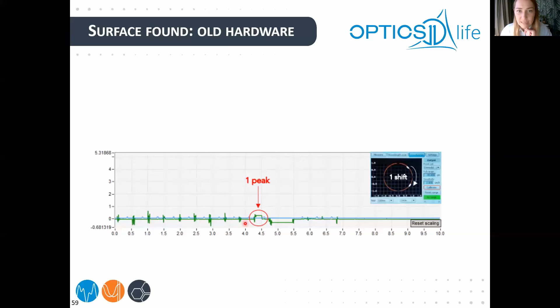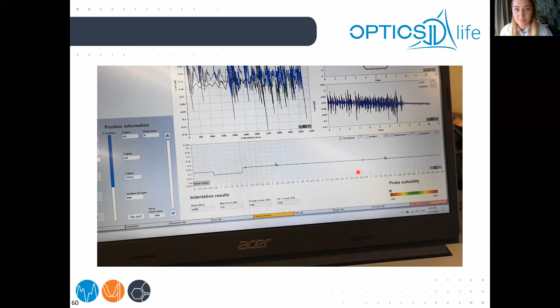Now, if you're not sure, you missed it, or you want to double check, you can just check manually. So what I did here, I moved down, and I see that there is a change in the baseline, and then I'm moving up, up, up, up, up, and here I'm out of contact. So I continue to move up and the baseline doesn't change. It means I'm out of contact. So then I can manually just bring back the probe to the contact. So this is a good check if find surface worked.